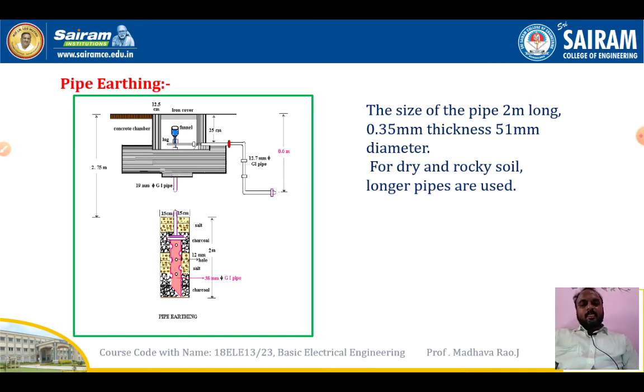The size of the pipe is a minimum of 2 meters long, 0.35 mm thickness, 51 mm diameter. For dry and rocky soil, longer pipes are used. So for dry and rocky soils, we need to use pipes longer than 2 meters, right? This earthing system should be kept away from the foundation of the building, a minimum of 1 meter away, otherwise the foundation of the building will be damaged.